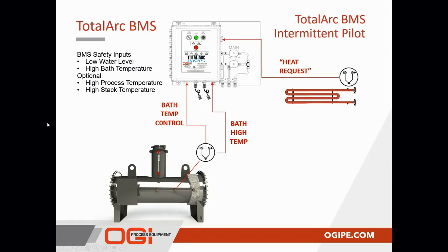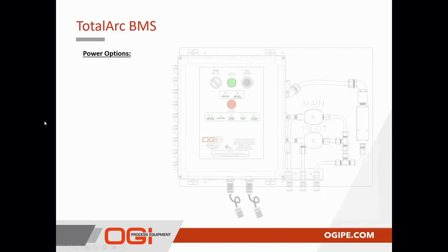Now that we've familiarized ourselves with the BMS operation, let's take a closer look at what options are available to power our BMS system. The primary operating voltage of our BMS is 12 volts DC, which provides the power for the solenoid valves, the relays, and the ignition module. The BMS power supply options provide basically all hardware that's necessary to convert the power from the supply voltage being supplied by the customer or as a part of the BMS package. All that power conversion is handled within the BMS itself.